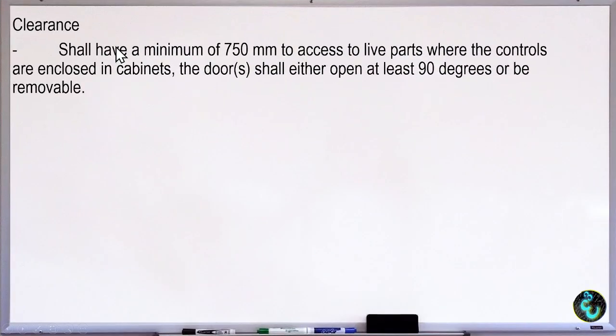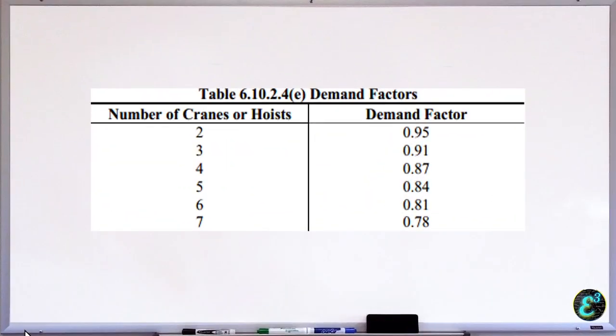Clearance shall have a minimum of 750 mm to access to live parts where the control are enclosed in cabinets. The door shall either open at least 90 degrees or be removable. So this is for the control of our cranes and hoists. Okay, so these are the demand factor for the supply of our cranes.